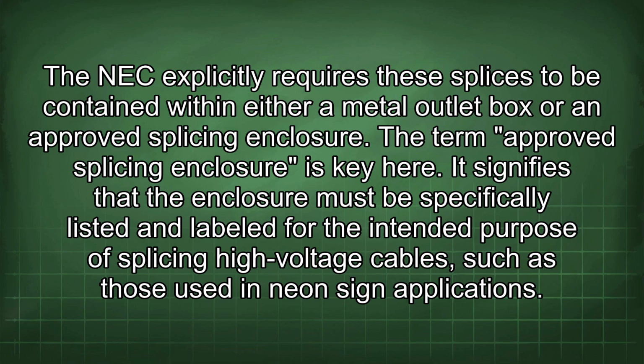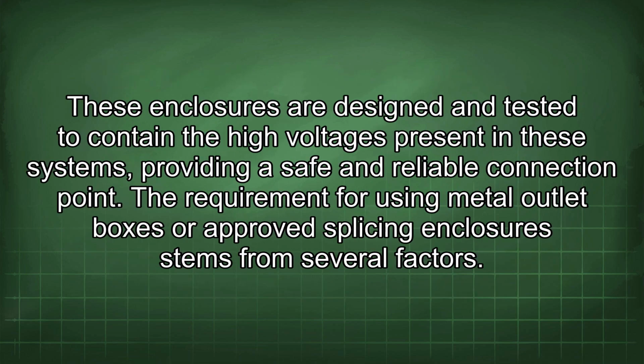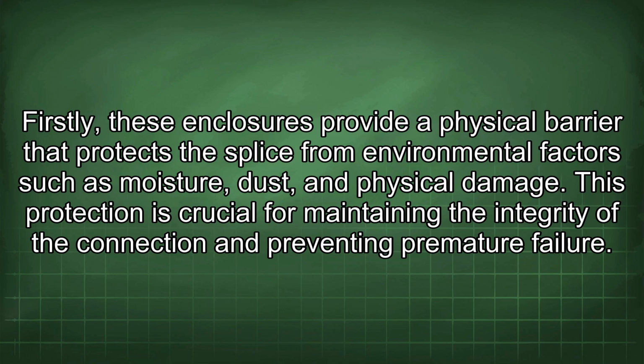It signifies that the enclosure must be specifically listed and labeled for the intended purpose of splicing high-voltage cables, such as those used in neon sign applications. These enclosures are designed and tested to contain the high voltages present in these systems, providing a safe and reliable connection point. The requirement for using metal outlet boxes or approved splicing enclosures stems from several factors. Firstly, these enclosures provide a physical barrier that protects the splice from environmental factors such as moisture, dust, and physical damage. This protection is crucial for maintaining the integrity of the connection and preventing premature failure.